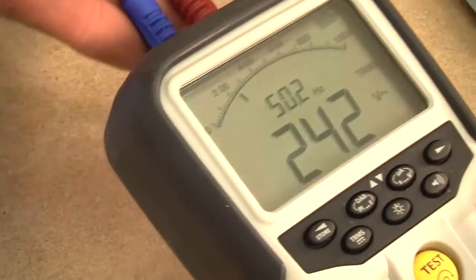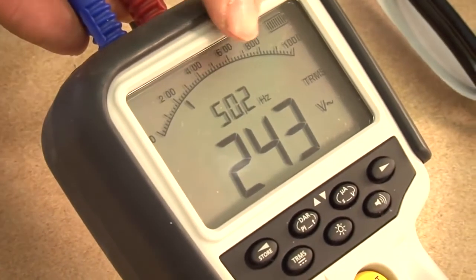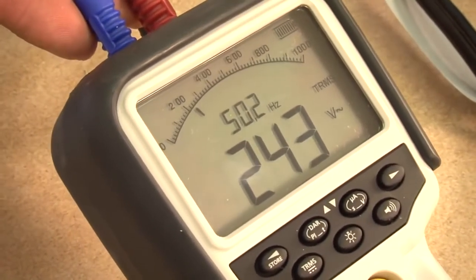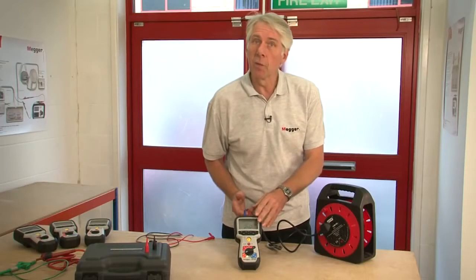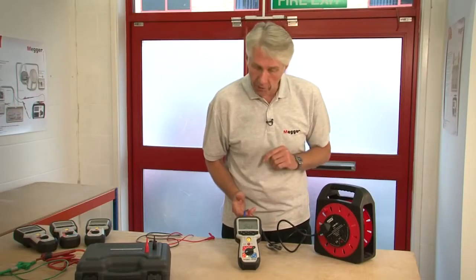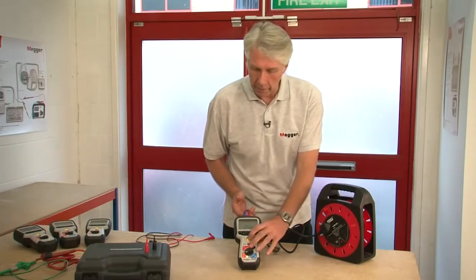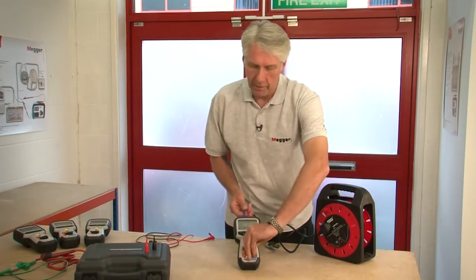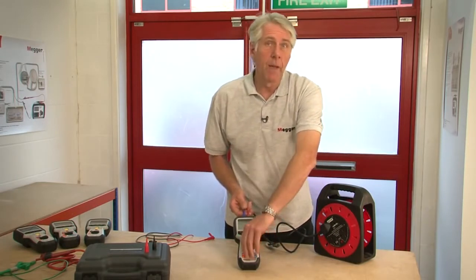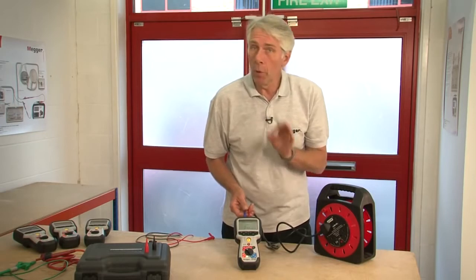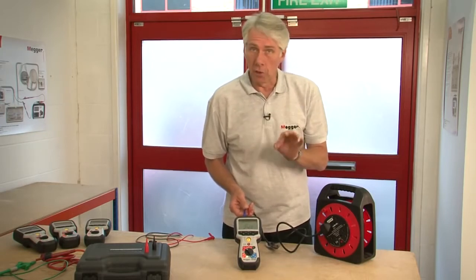Now you'll see that the product immediately warns you of a live voltage by repeatedly sounding the buzzer, and it automatically changes to a voltage range showing the actual voltage that's present. Now I can push the test button, I can select different ranges, and it will not damage the instrument, and more importantly, it won't damage you.